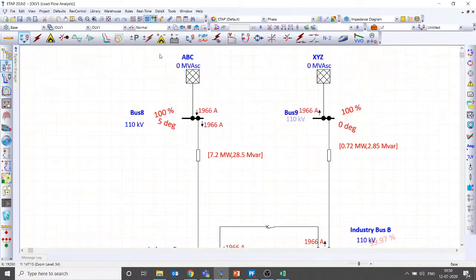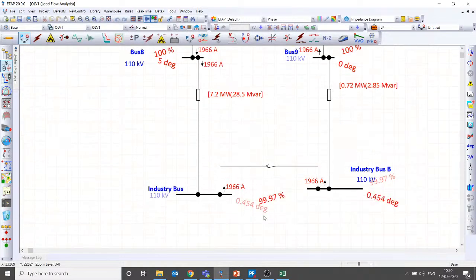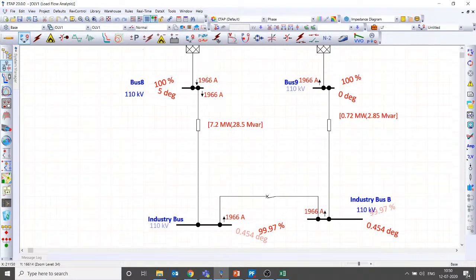But if you connect two different sources here, there will be an uncontrolled power flow through your industry bus. That's because of not just the voltage mismatch, but also the angle mismatch. Whenever there is an angle mismatch, there will be an uncontrolled real power flow. And if there is a voltage mismatch, there will be an uncontrolled reactive power flow. And of course real and reactive power depend on each other, so whenever there is a real power flow, automatically there will be a reactive power flow as well. Yes, hope that is clear. That's to answer a question from Sasi Kumar.